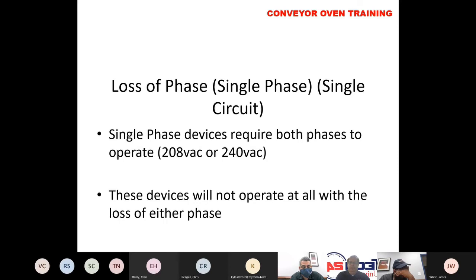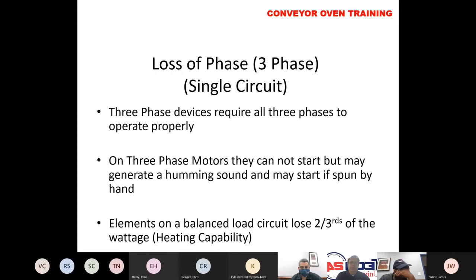When we're checking our voltages, if we lose a leg or a phase of voltage or potential on an oven that's 208 or 240, that is a single phase system, the oven's not going to operate at all. If we lose a leg on 3-phase, if the 2 phases still present are part of the control voltage, then the oven may still appear to operate. 3-phase motors, when they are not given all 3 phases, tend to hum and may bounce back and forth. And you'll lose 2/3 of your wattage capacity on a balanced 3-phase electric load for heating elements if you lose 1 leg of voltage.